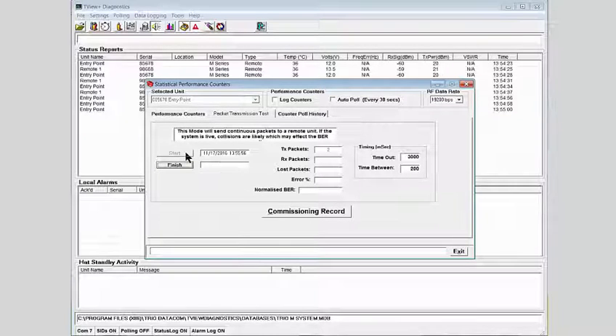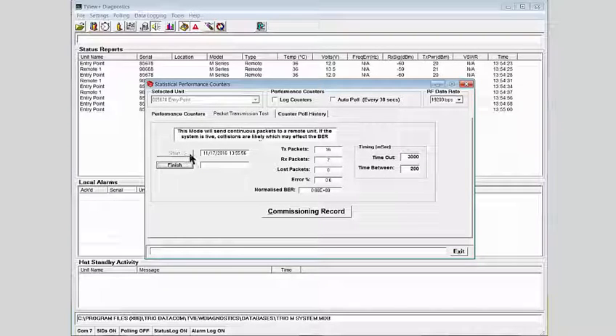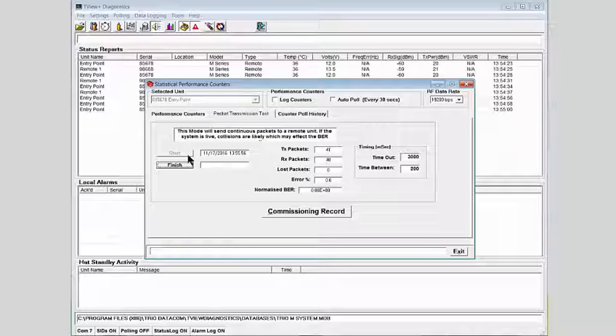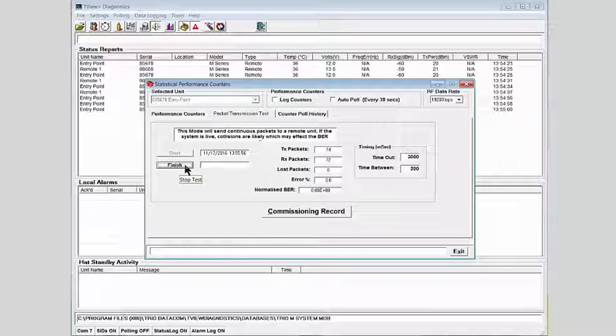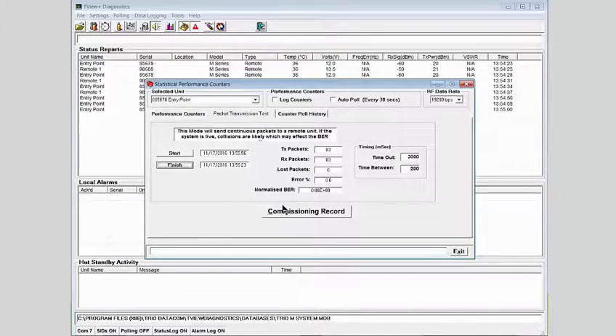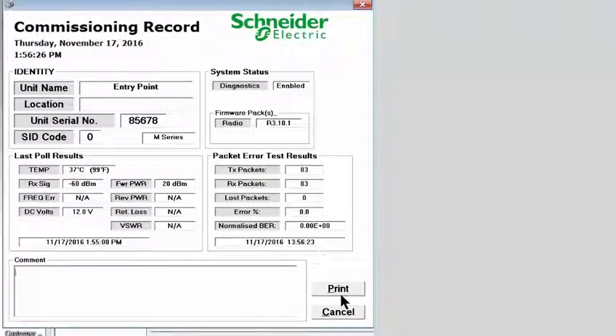I'll click the Start button, and we can see now that there is over-the-air traffic. The radio LEDs are flashing rapidly as messages are sent to the far end. The far radio, the entry point, detects these are test packets, loops them back internally, and if the radio that originates the traffic gets them back, we have a successful receive packet. When we have decided that the test is complete, we click the Finish button. We can now click the Commissioning Record button, and if desired, print a report for later use.